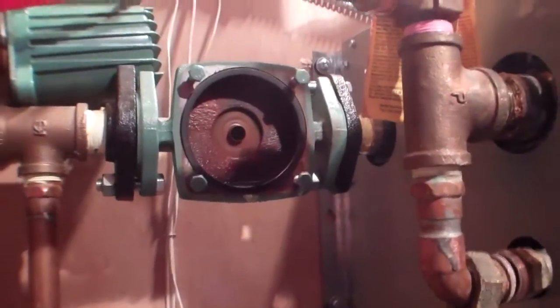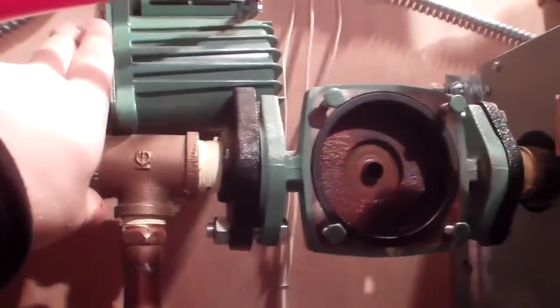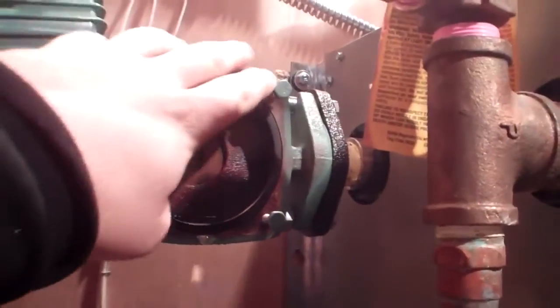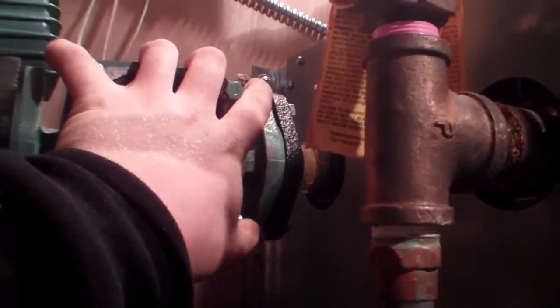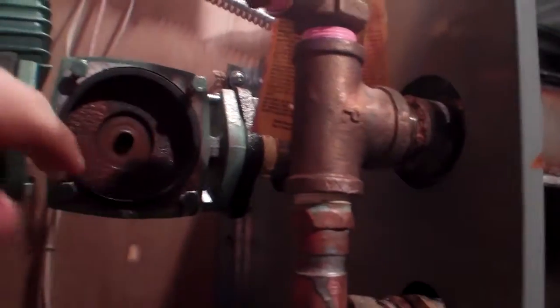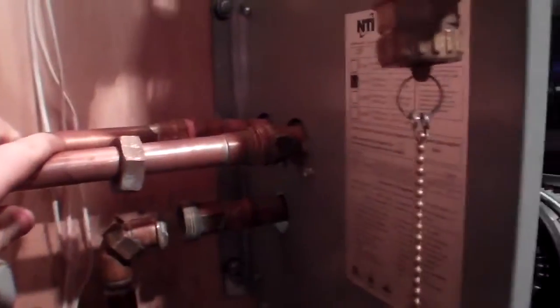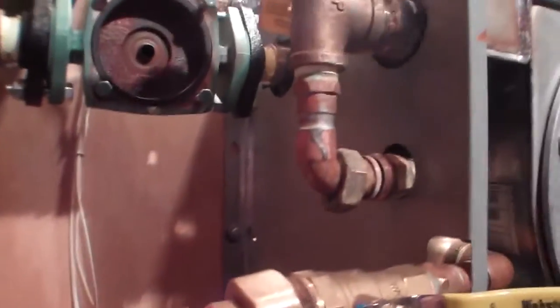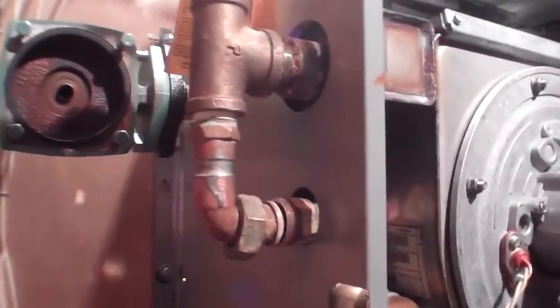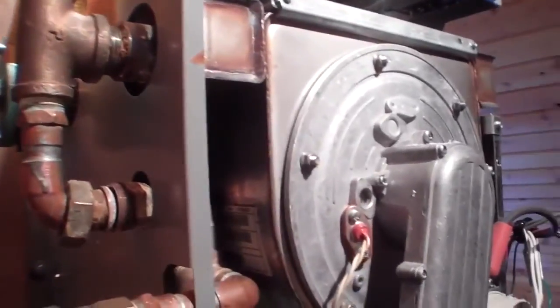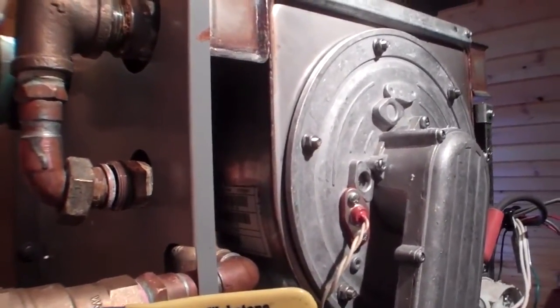So now you see I removed the pump here and I'm getting ready to disconnect all my connections here to the top of the heat exchanger. And I just purged the whole system out and got it completely free of water. So we can get ready to pull this thing off the wall and dismantle this unit on a table so it's a little easier to do it that way instead of trying to do it up top because you have your exhaust here.